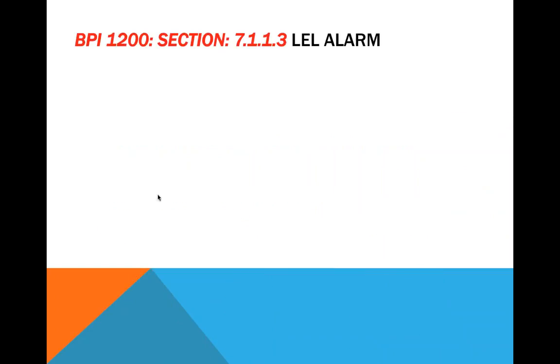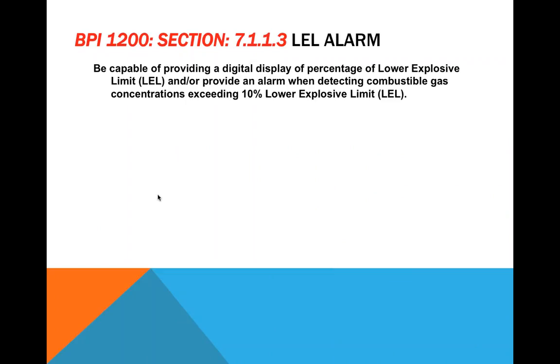Now jumping over to BPI 1200, which we cover today, section 7.1.1.3 talks about an LEL alarm. This is a phrase directly from the standard: the device, the combustible gas leak detector, must be capable of providing a digital display of % LEL or provide an alarm when detecting combustible gas exceeding 10% LEL. So this is part of the new BPI 1200 standard, which is in effect and should be enforced at this point.